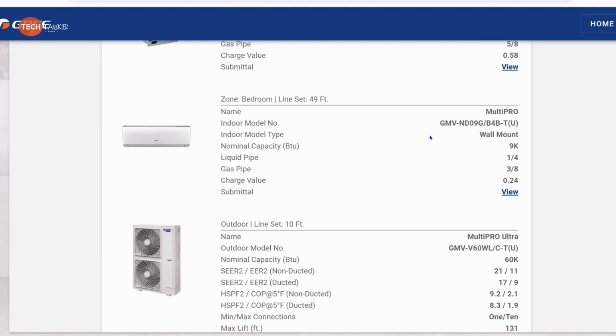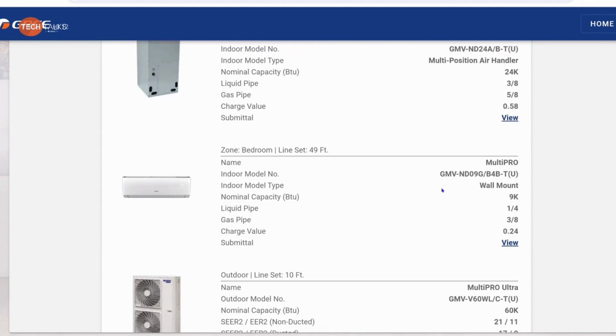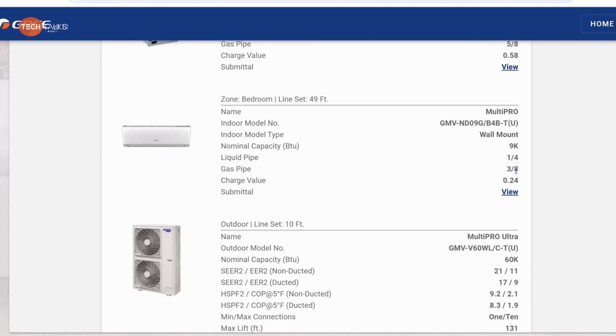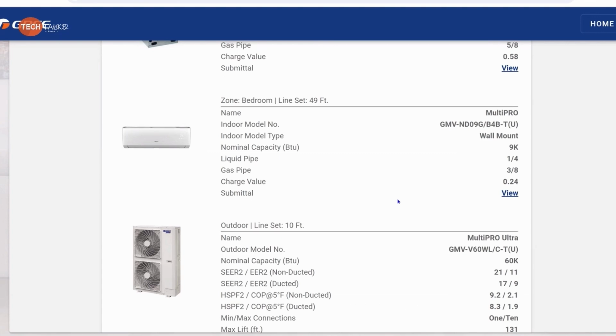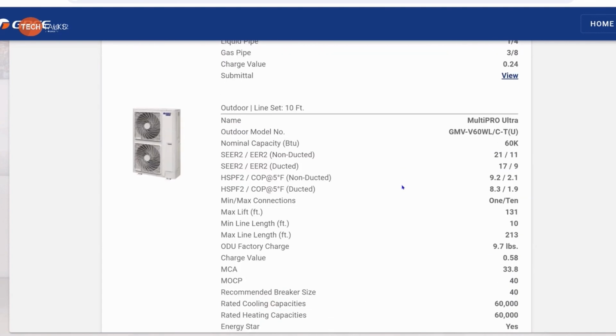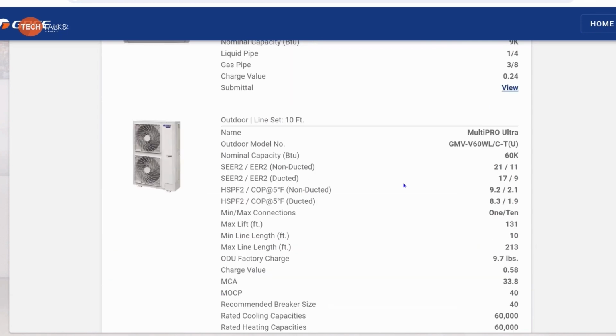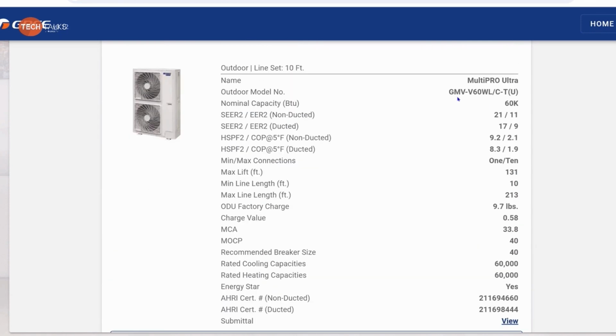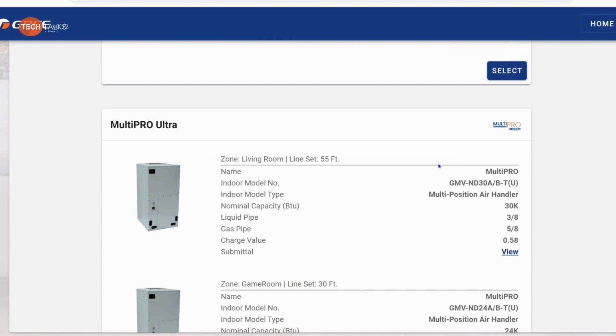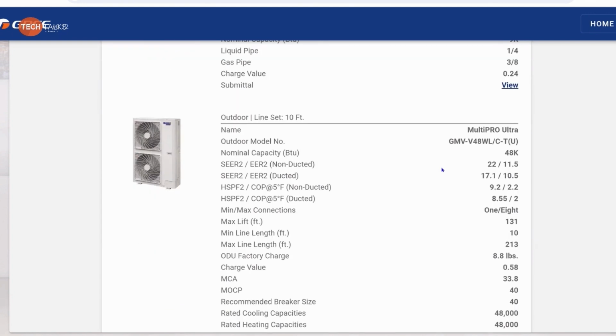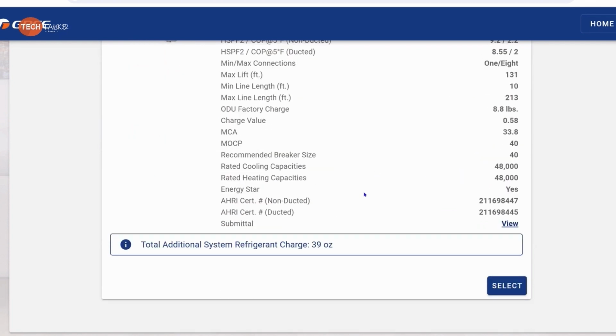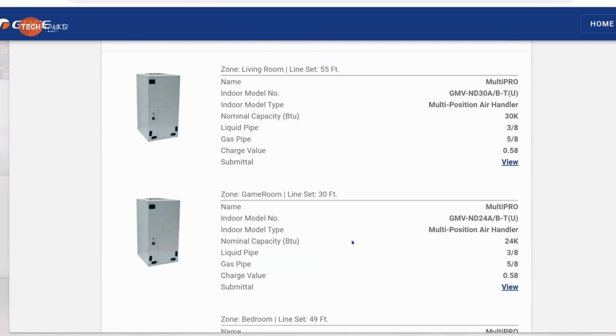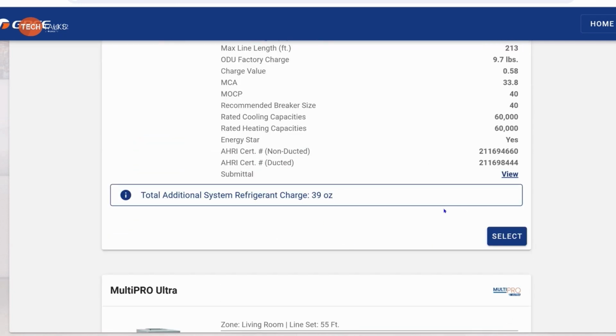Then we have the 9K wall mount, and pipe sizes are 1/4, 3/8, and our multiplier for that is 0.24 for a refrigerant. Okay. Now, what I want to show you is, it's given me the ability to do the 5-ton condenser, but I can also do it with a 4-ton condenser because my connection capacity is still within allowable, okay? So total refrigerant charge there is 39 ounces, and this one's 39 ounces.